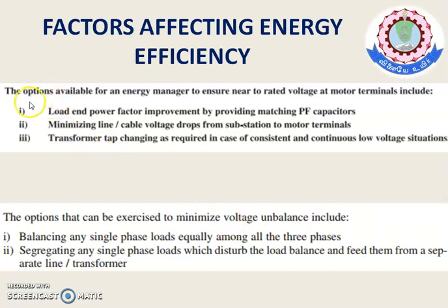Another, the options available for the energy manager to ensure near-rated voltage at the motor terminal include load end power factor improvement by providing matching power factor capacitors, right? So you need to attach external capacitance at the load end to minimize the reactive power consumption, so that the voltage at the motor terminal will be nominal, right? Will not be a low voltage, right?